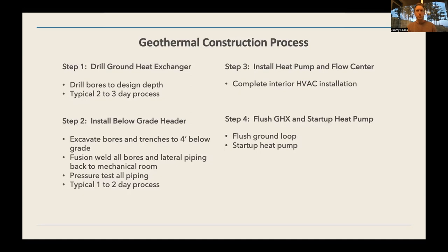Once those vertical boreholes are installed, they need to be connected with horizontal piping and buried 4 feet from finished grade. So if we were to drill those boreholes in the driveway area, there's a small amount of trenching that gets done for your below-grade header.